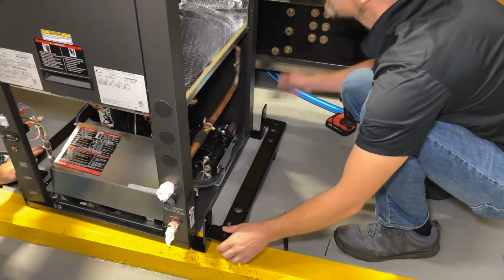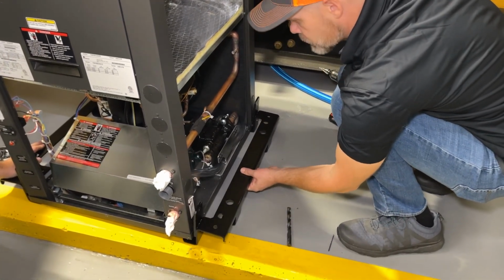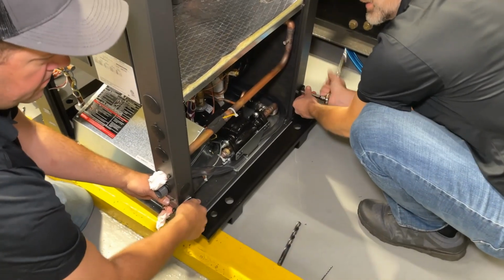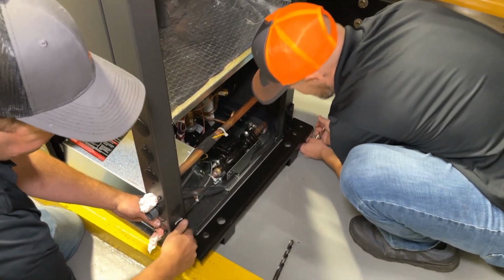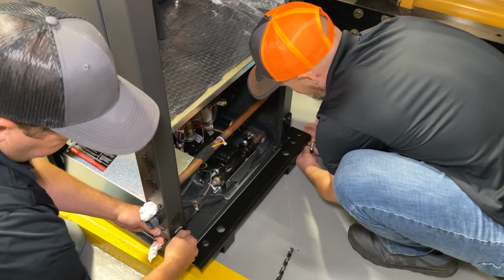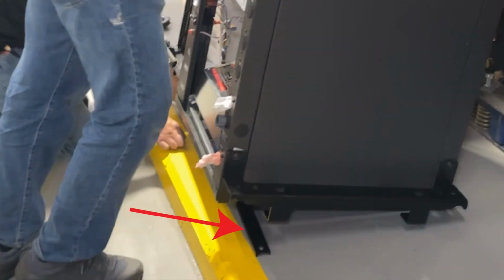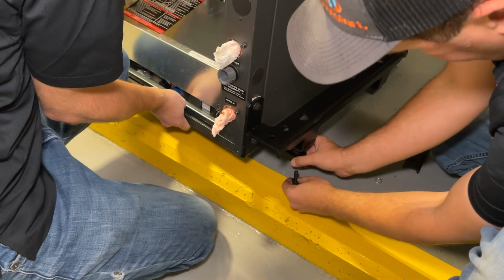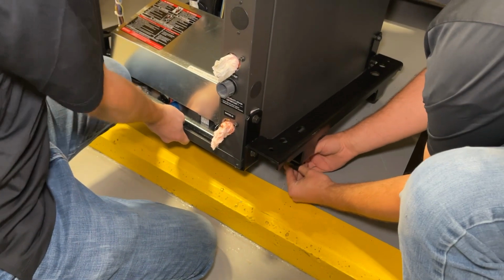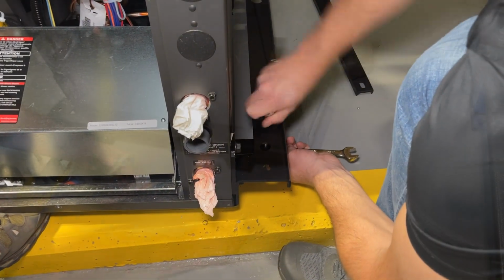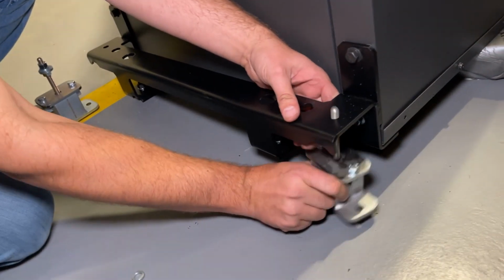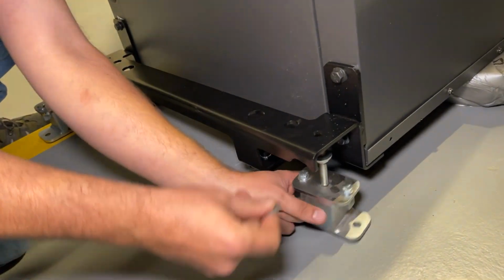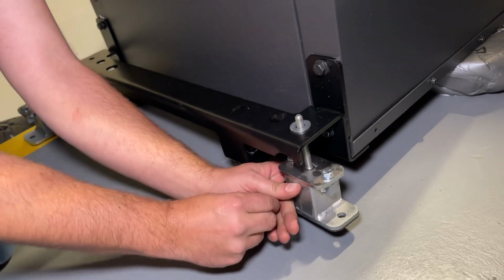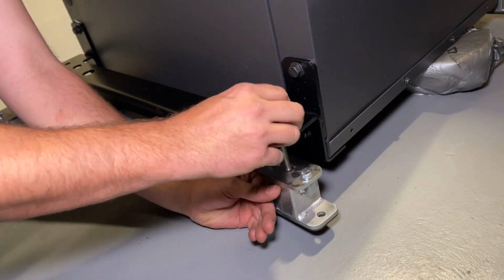Once all holes are drilled, slide the bracket back into position and secure with provided hardware. Repeat on the other side. Once brackets are secure, install 2 cross-supporting brackets, ensuring the assembly is square. Next, install spring mounts to the 4 corners of the assembly. Adjust each spring mount so that the bottom washer measures 1 1/4 inches from the top of the mount.